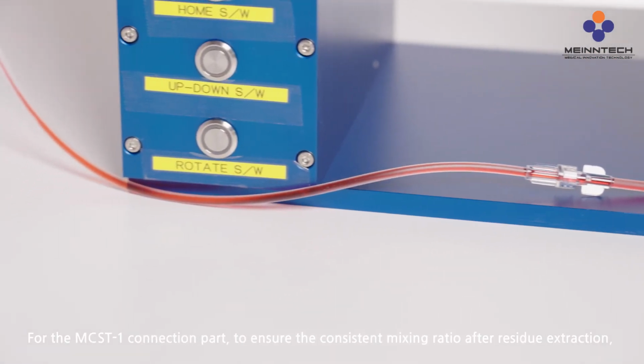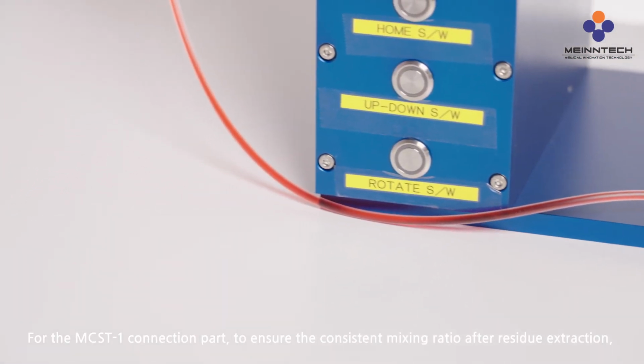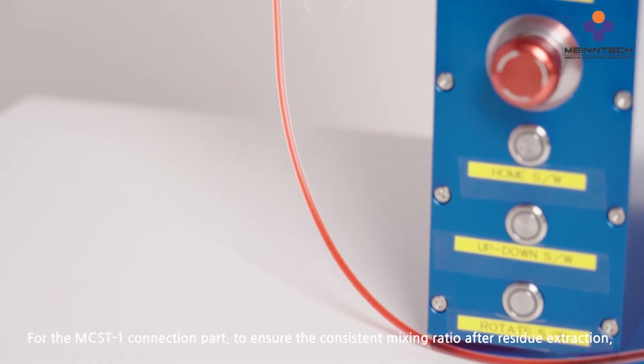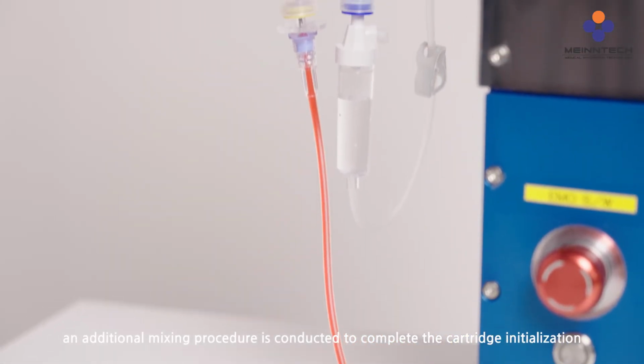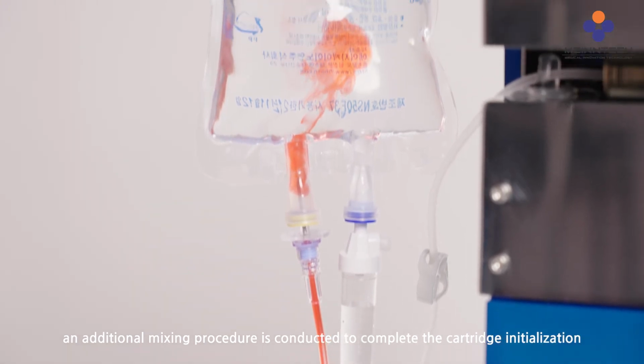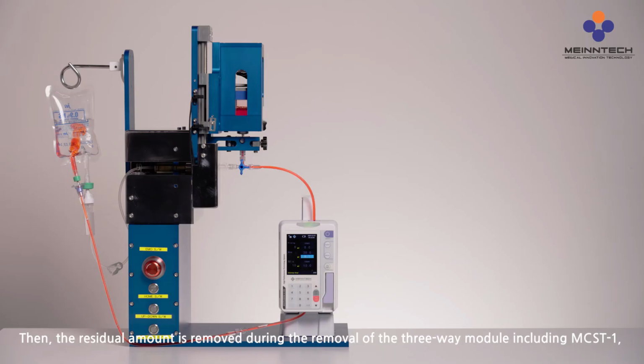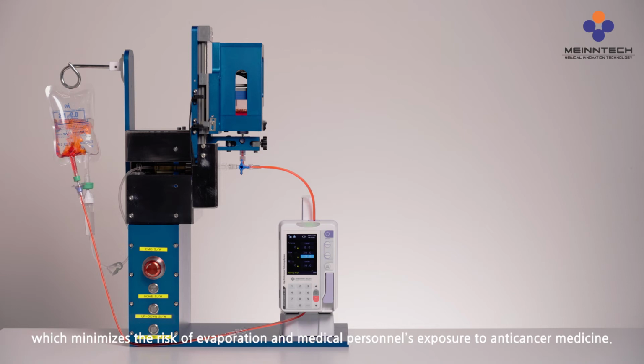For the MCST1 connection part, to ensure the consistent mixing ratio after residue extraction, an additional mixing procedure is conducted to complete the cartridge initialization. Then the residual amount is removed during the removal of the three-way module including MCST1, which minimizes the risk of evaporation and medical personnel's exposure to anti-cancer medicine.